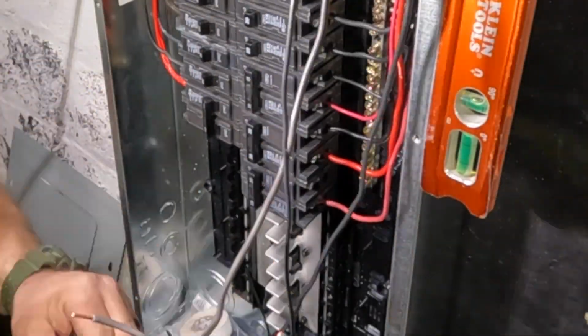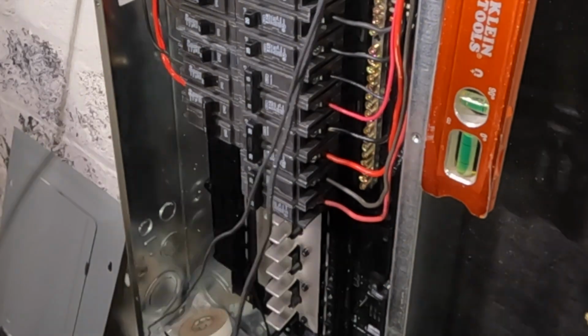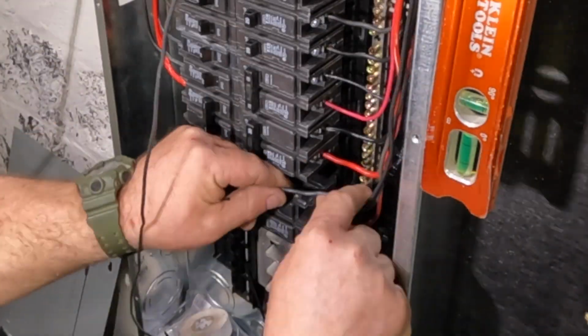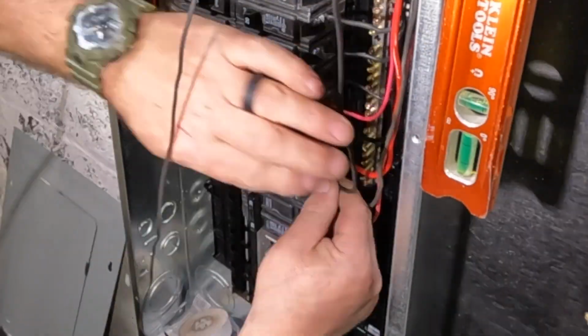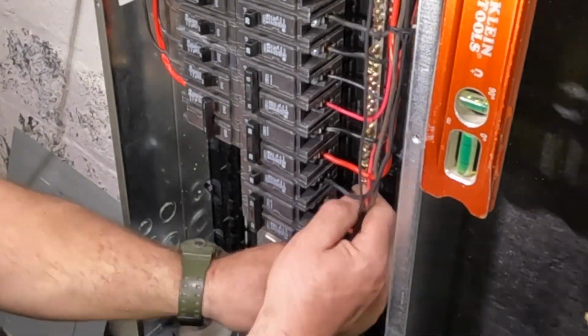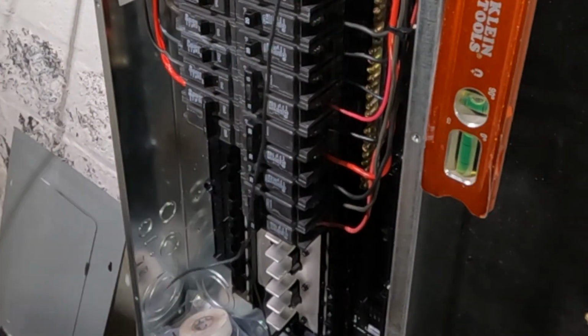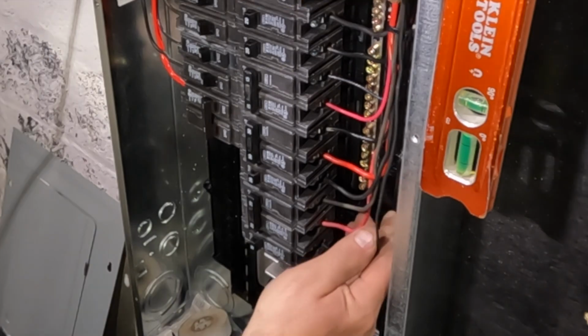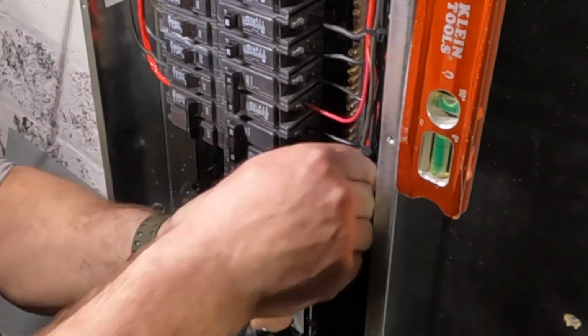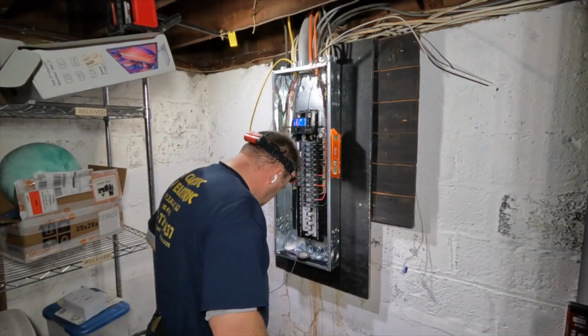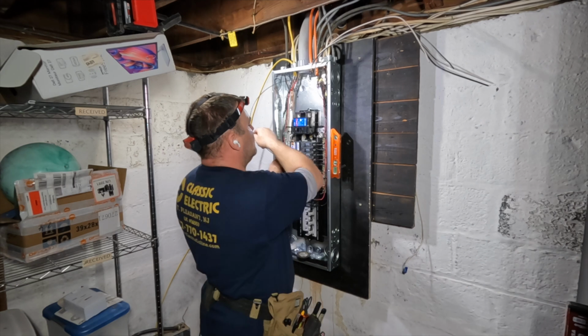The least amount of wire nuts you can put inside the panel, the better—I think it looks neater. Of course, it's permitted to use wire nuts or connectors inside a panel as long as you don't take up more than 40% of that cross-sectional space, which would be a lot of wires. I never come close to violating that code section.